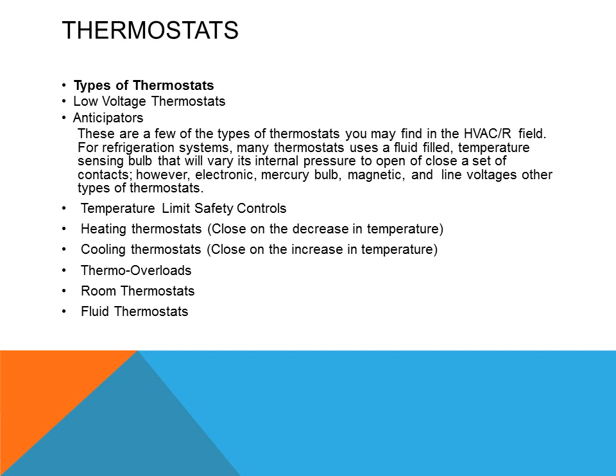There are several types of thermostats in the HVAC field. For refrigeration systems, many thermostats use a fluid-filled sensing bulb that expands by pressure built up from temperature changes, opening and closing a set of contacts. Other types include electronic, mercury bulb, magnetic, and line voltage thermostats. Heating thermostats close contacts on a decrease in temperature, while cooling thermostats close contacts on an increase in temperature.